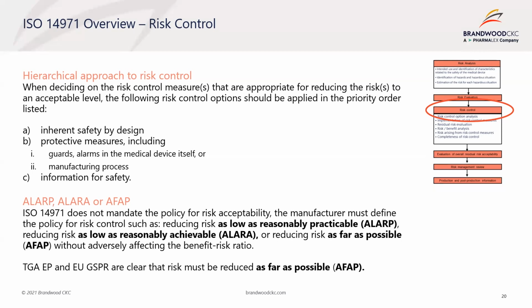I just want to briefly discuss risk acceptability. ISO 14971 does not mandate a policy for risk acceptability. The manufacturer must define a policy for risk control, such as reducing risk as low as reasonably practicable, reducing risk as low as reasonably achievable, or reducing risk as far as possible without adversely affecting the benefit-risk ratio. It is important to note that only AFAP does not allow economic considerations for mitigating risks. That is, risks must be reduced as far as possible without economic or business considerations. Both the TGA, EP, and EU GSPR are clear that risk must be reduced as far as possible.